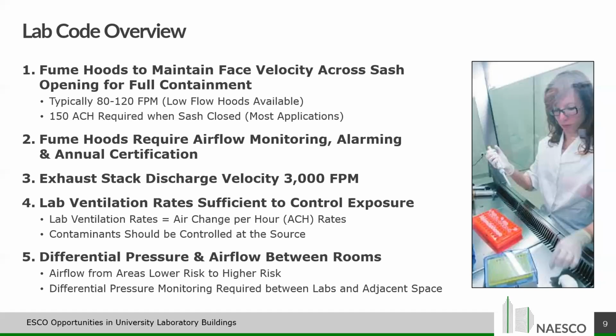And then it comes down to lab ventilation rates, turning the air over in the labs. The code's a little gray here. It's not prescriptive. It says it just needs to be sufficient to control exposure. And those air change per hour rates are key to energy savings, and you'll hear us talk about that quite a bit today. It also says that your contaminant should be controlled at the source. So it's a bad lab practice to leave chemicals out in a lab. They all should be stored in a ventilated storage unit, not in the fume hood. And when you do that, you have a safer lab, and your ventilation rates are certainly allowed to be lowered.